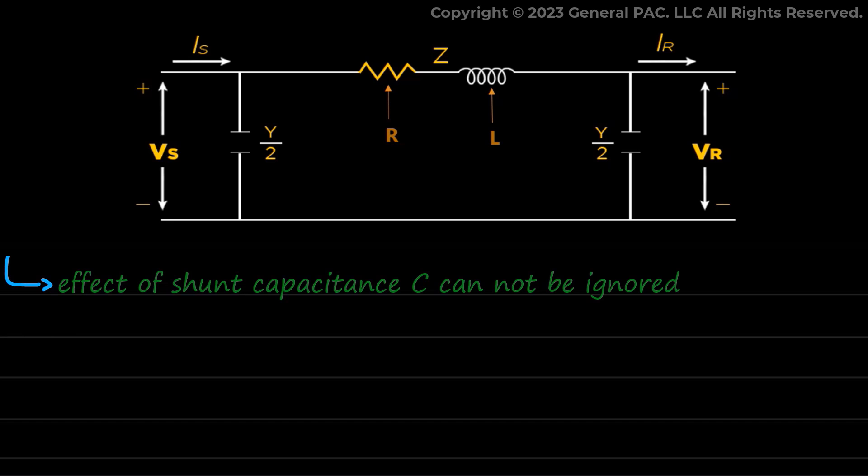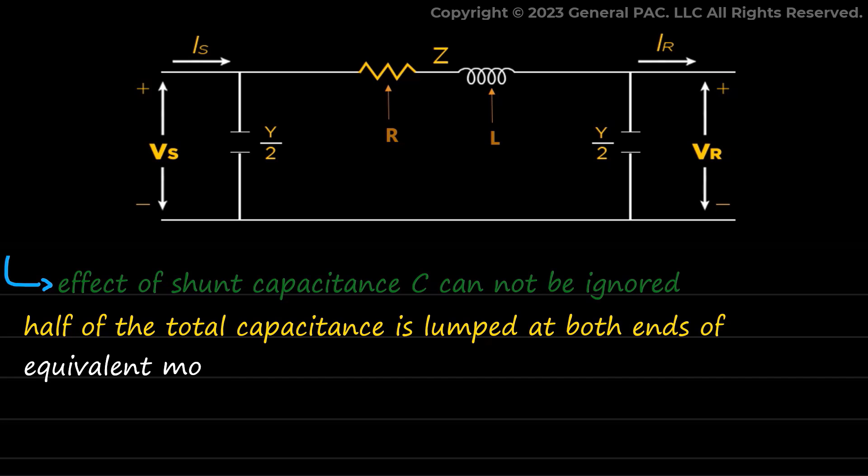Now there may be two ways to represent the shunt capacitance. Half of the total capacitance is lumped at both ends of equivalent model of transmission line in the nominal pi modeling of medium transmission line, or the capacitance may be lumped at the center of medium transmission line in the T model. We will explain the nominal π and nominal T model of medium transmission line now.